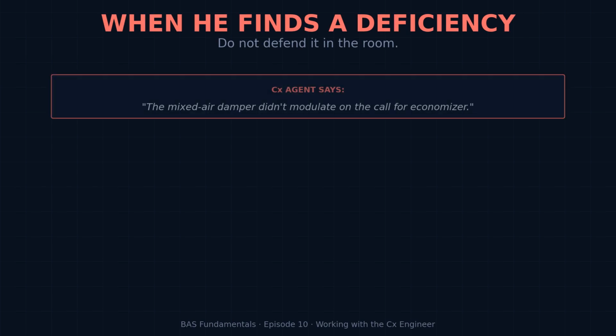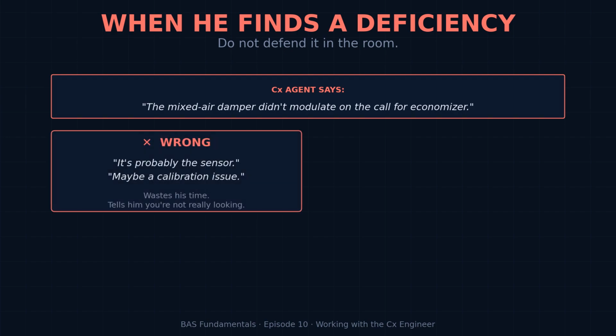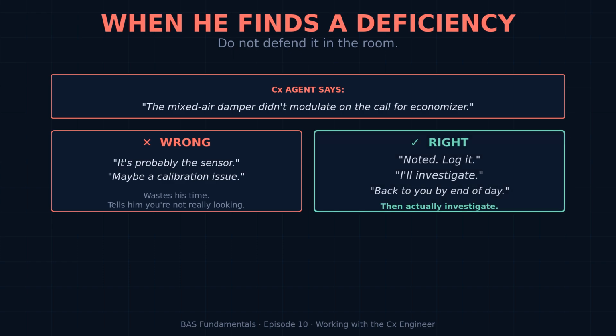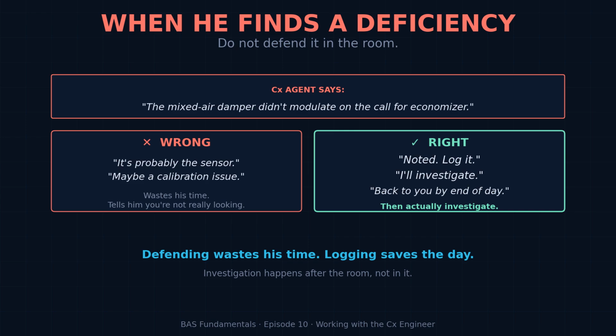And here is the key. When he finds a deficiency, and he will, do not defend it in the moment. He says, the mixed air damper did not modulate on the call for economizer, and the sequence says it should have. Do not say, it's probably the sensor, or maybe it's a calibration issue. Say, noted. Let's log it. I'll investigate. Get back to you by end of day. Then you actually investigate. Because defending in the moment just wastes his time and tells him you're not really looking.